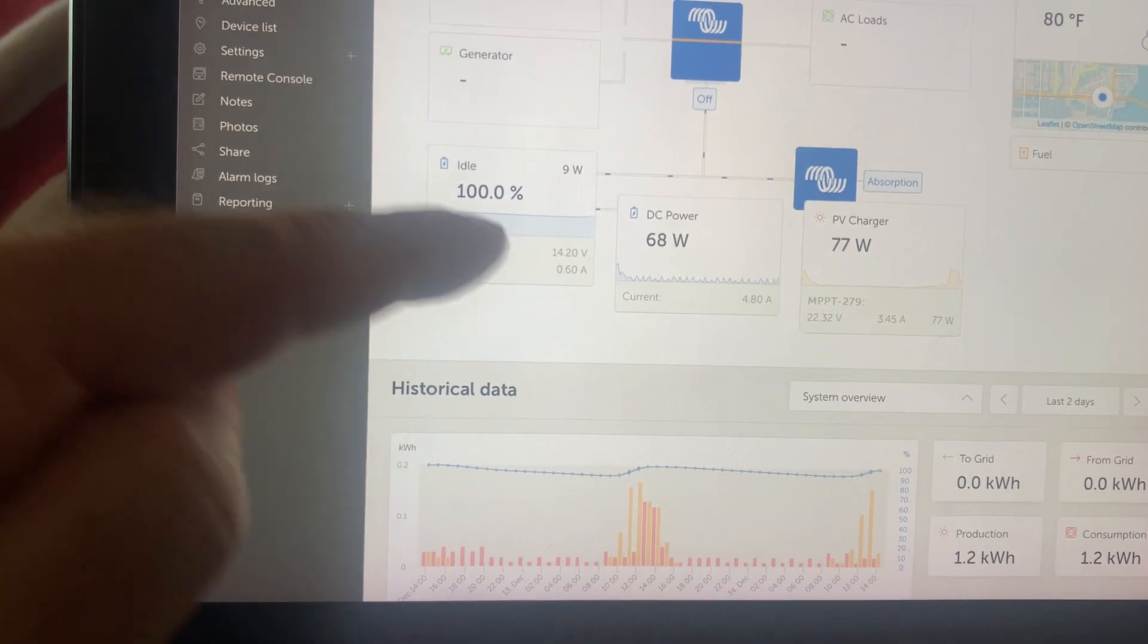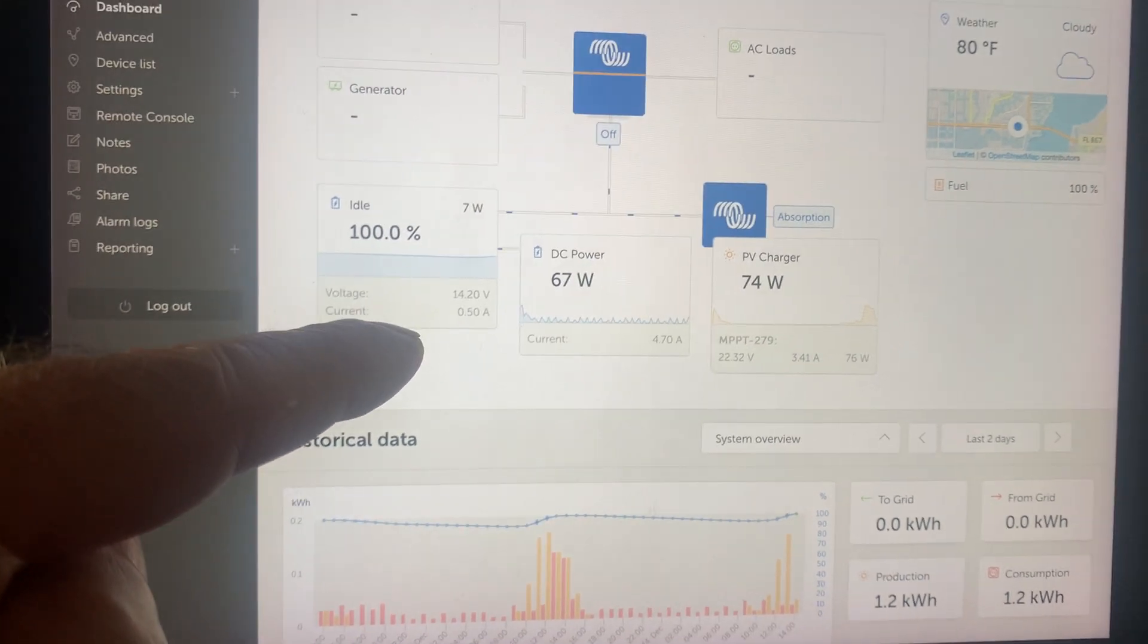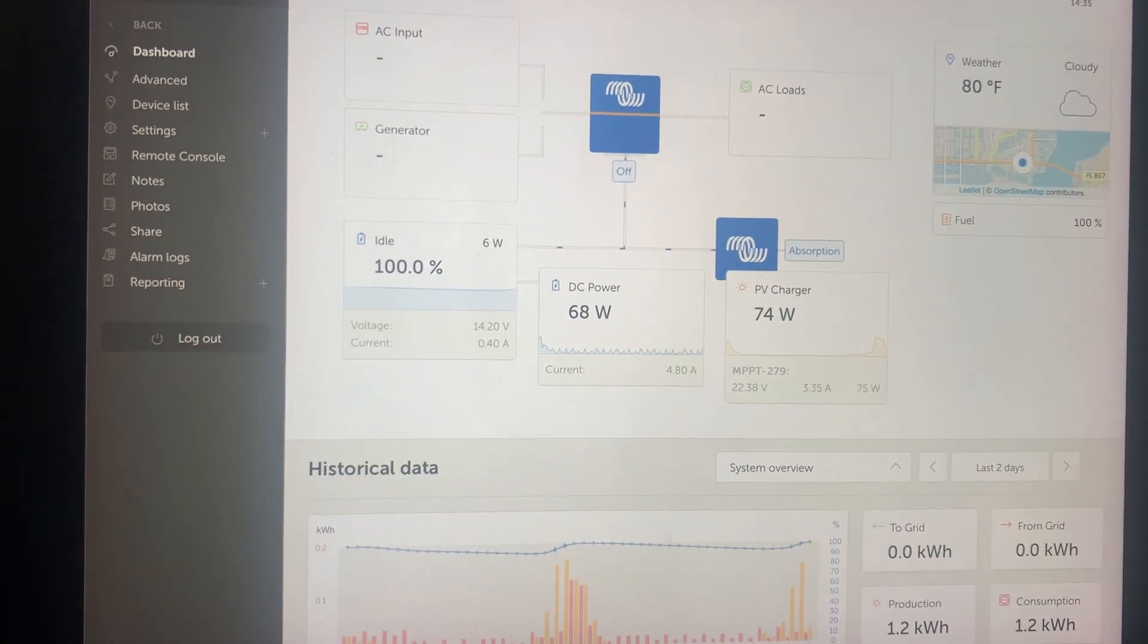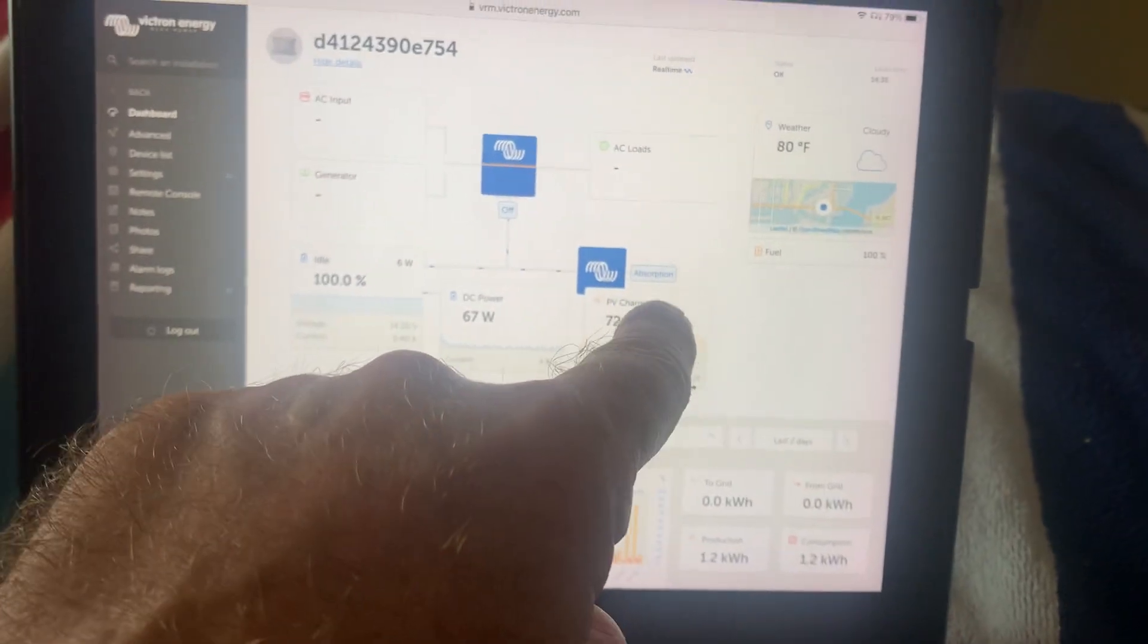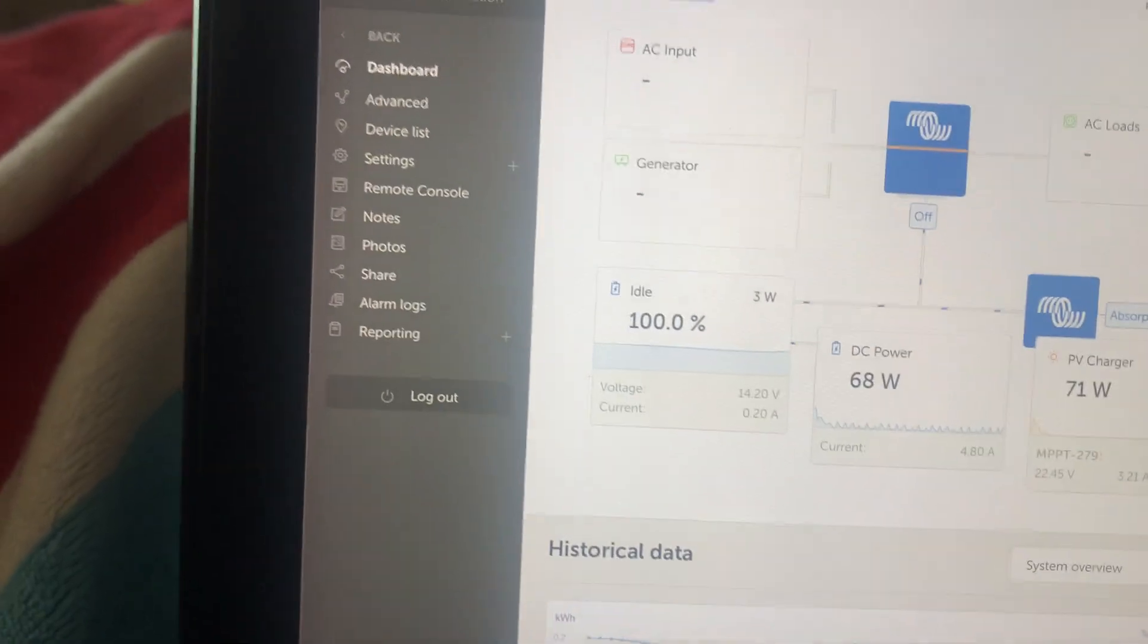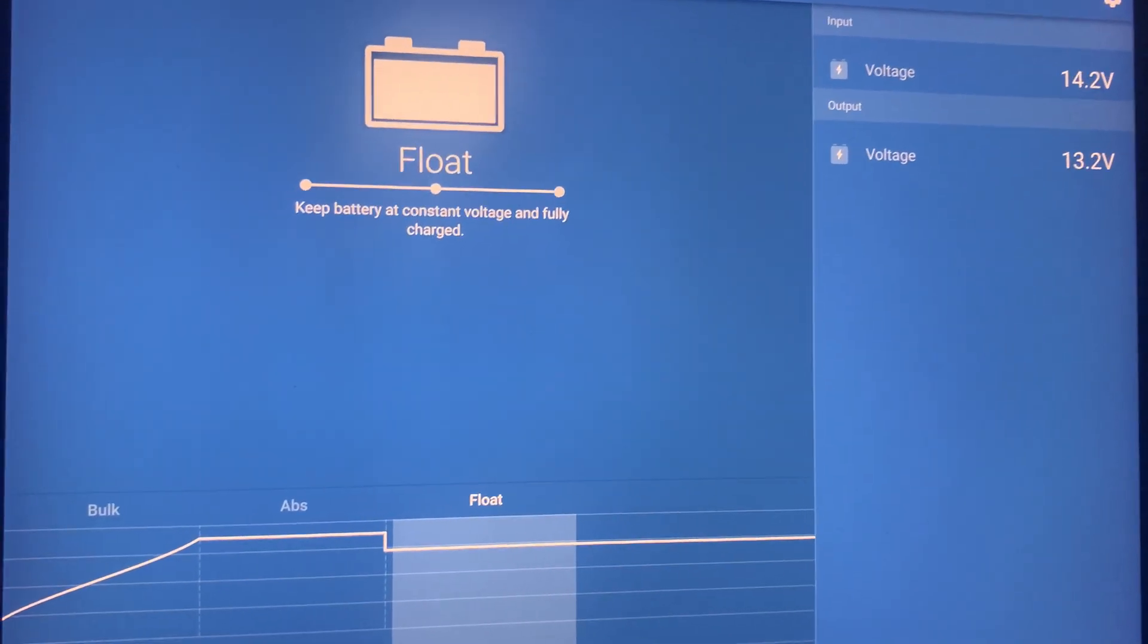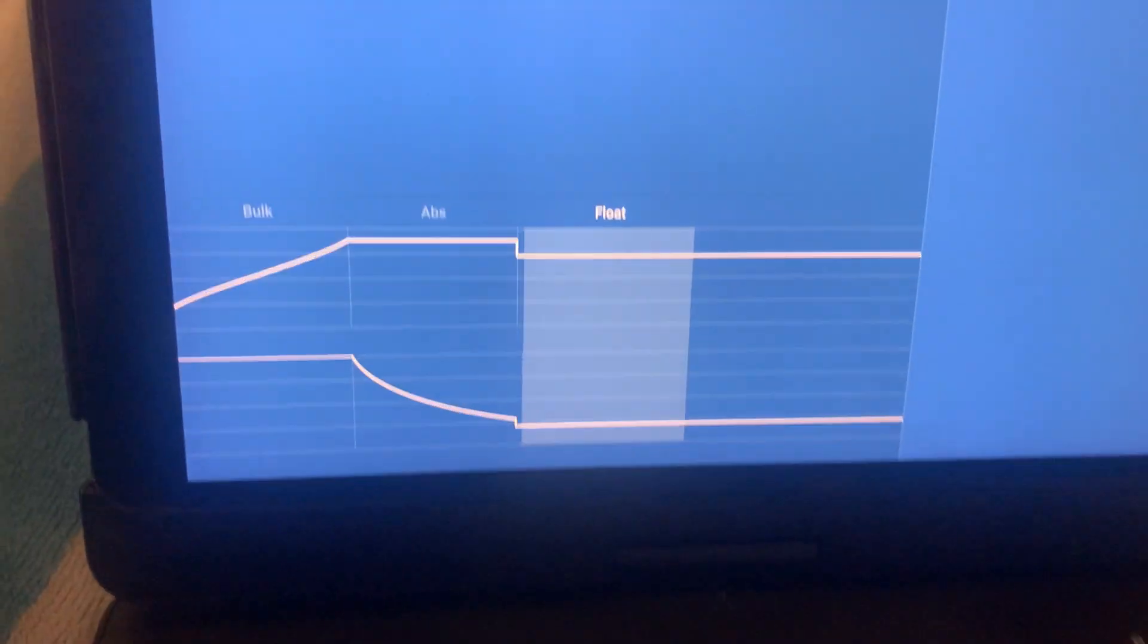It's not drawing down the voltage on the main battery at 14.2 because the hit is so light. And now we've got this guy here in absorption. And he will hit float pretty soon because there's no real heavy load on it. And the other battery from the Orion charger is now at 13.2. So he has gone into float.